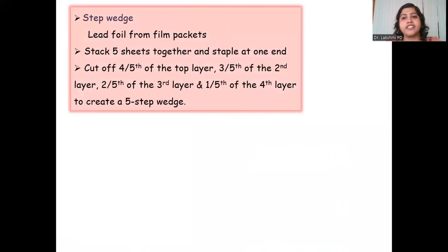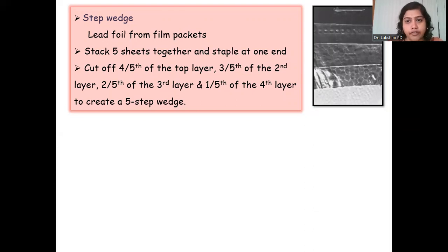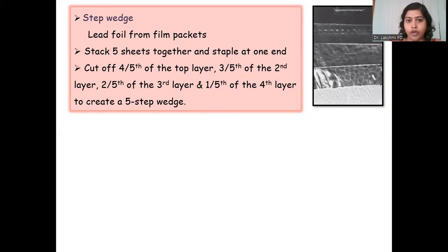A much more cost-effective method is the step wedge technique, in which you use nothing but discarded lead foils from used film packets. You need five lead foils and staple them together. Then you cut off layer by layer: cut off four-fifths of the topmost layer, three-fifths of the second layer, two-fifths of the third layer, one-fifth of the fourth layer, and you will get a five-step wedge.